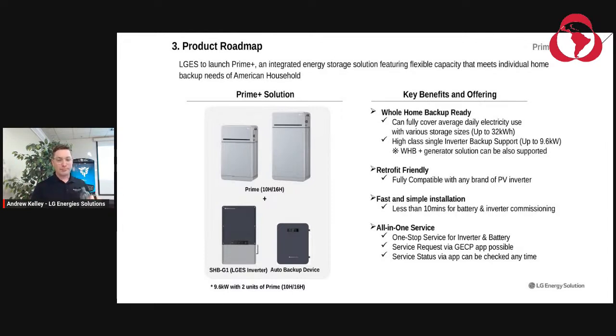How much PV power can be added through the plus inverter? Is that AC coupled, right? This one's AC coupled, so it's completely separate. So what's the maximum PV you can couple with this inverter? It depends on your application essentially. So you have 200, you can connect to your 200 amp main service panel. Basically it's a 40 amp backup, so it'll accept 40 amps of input as well.